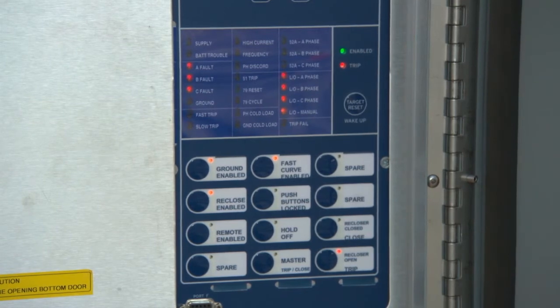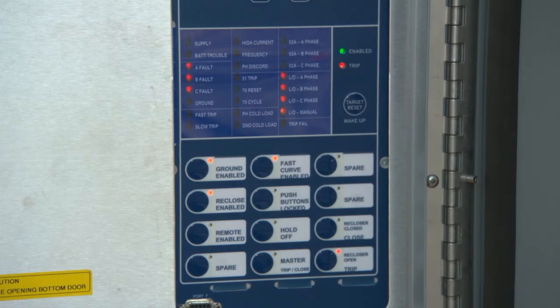After successfully closing the manual operating handle, the red light will turn off. You can now close the system using the master and close buttons. All three of the phase indicator LEDs and the 79 reset LED on the panel turn green, and the system is now in its normal operational state.